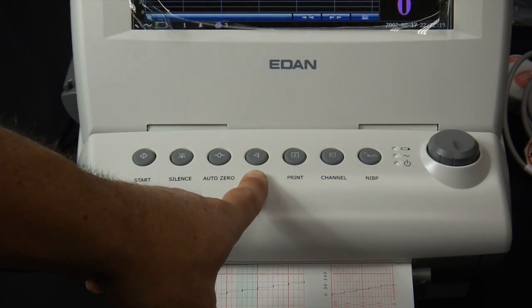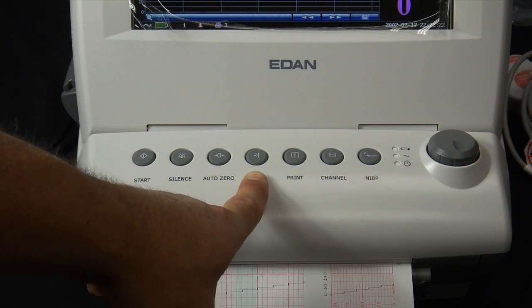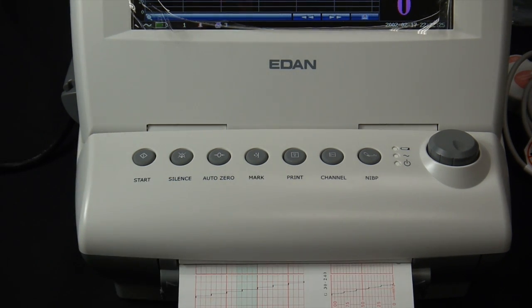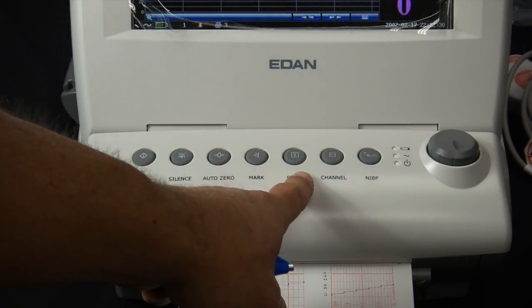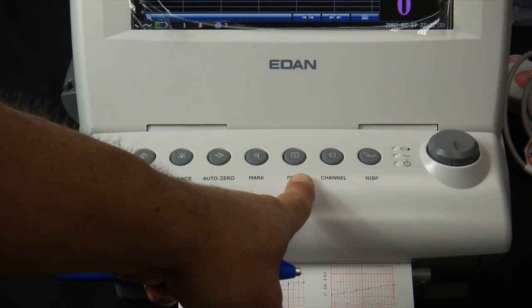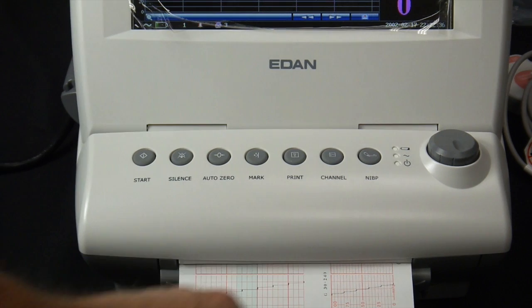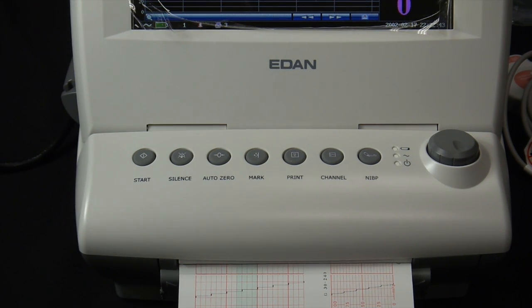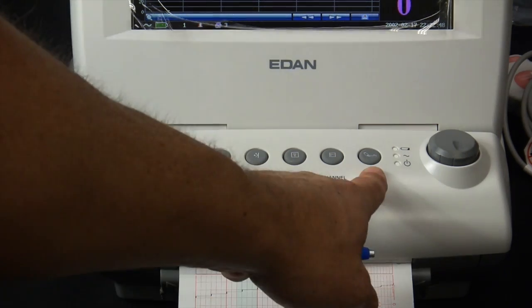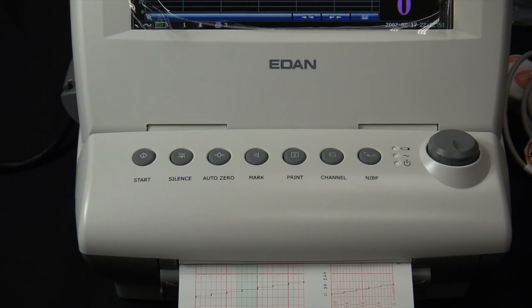To the right of that is the mark button. That will record an event, similar to pressing the event marker button that is external to the monitor. To the right of that is the print function. That starts or stops printing. It's a toggle between start and stop. To the right of that, the channel button. That will switch between fetal heart rate from ultrasound 1 and ultrasound 2, or FHR1 and FHR2. And then the far right is the NIBP button. That will start or stop an NIBP measurement. Not all of these monitors are equipped with maternal functions, so that NIBP button is a function of a maternal capable unit.